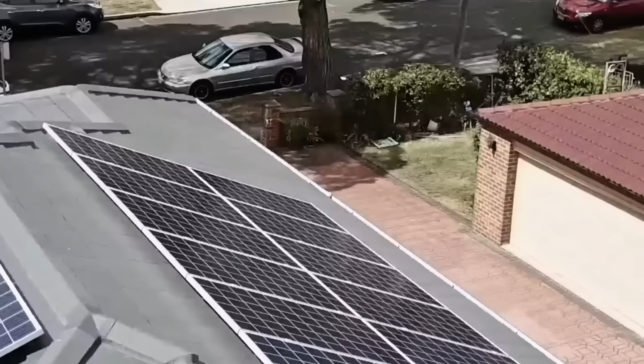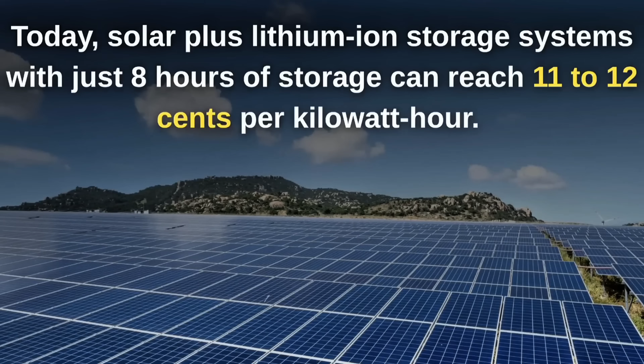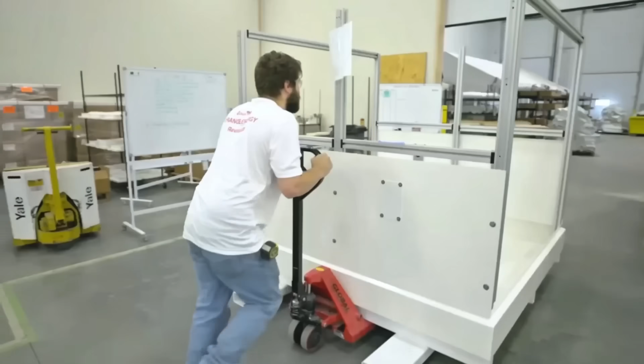To put that in perspective, on-site natural gas generation, which is what many desperate data centers are turning to while they wait years for grid interconnection, starts at 4 to 5 cents per kilowatt hour and can escalate to 8 cents or more depending on the site and fuel prices. Traditional grid power varies by region, but is climbing steadily everywhere.